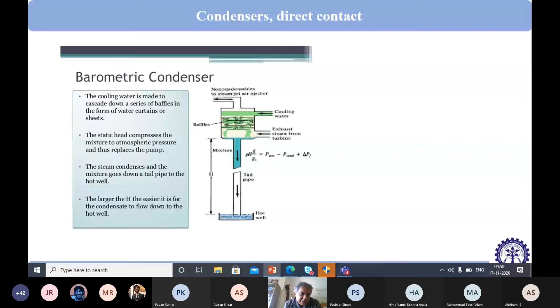So basically it is designed in such a way that steam will be totally condensed, only the non-condensable gas will go out, and the mixture of water and steam condensate will be collected. These are made of a larger height so that there could be some amount of compression. Why am I calling it compression? I already told you about pressure matching: from the turbine, the steam is coming at a pressure much below atmospheric pressure. So its pressure has to be increased to atmospheric pressure. That's why compression is needed, and that is done with the help of the water height. Please read the description over here, you will get something more.